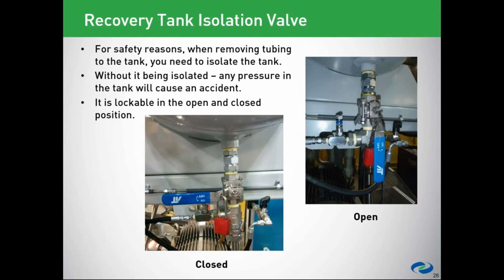So the recovery tank isolation valve: the tube that goes out the bottom of this valve basically goes to the PRV. So this is a way we can block it and bleed it, and it makes it a little safer for us to remove that PRV, or SRV in some cases. It depends on what you call it. Same job. It's a lockable valve. It locks in the open and closed position, so nobody can mess with it. Here we're doing a lockout tag on it, but I would probably use something a little more secure than that.